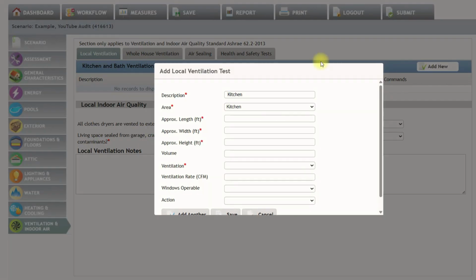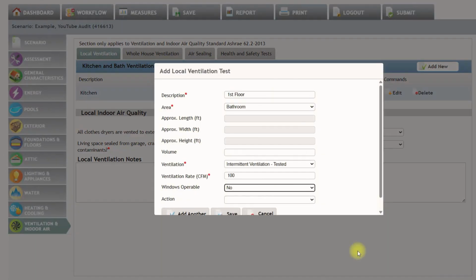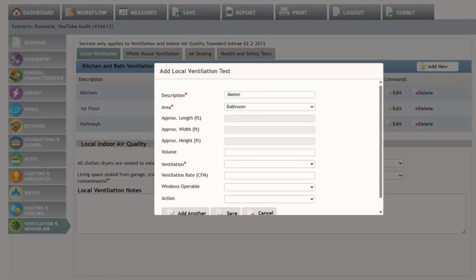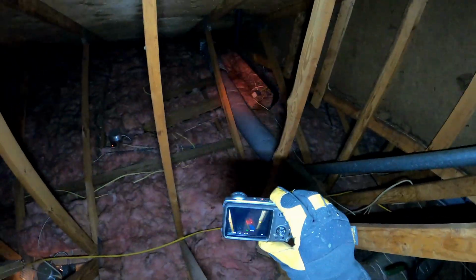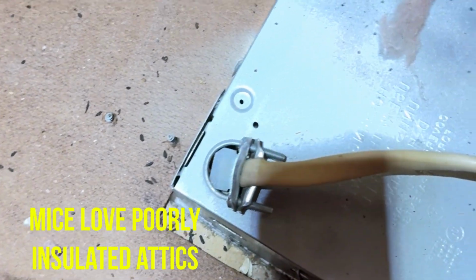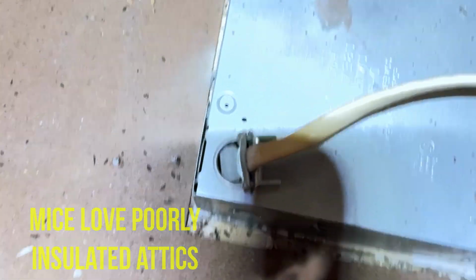While I'm in here, I also log the ventilation findings. Two bath fans were vented to the attic, and one wasn't pulling any air at all. These details matter because proper ventilation ties directly into indoor humidity and long-term comfort, especially in a home with 5 occupants.